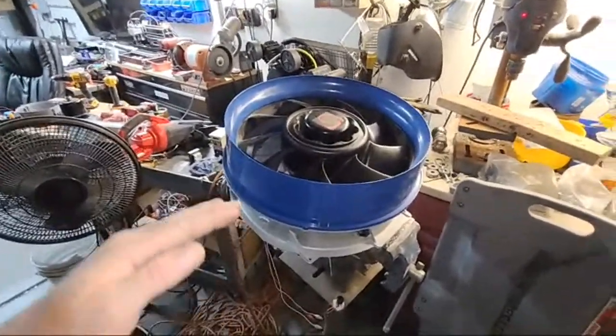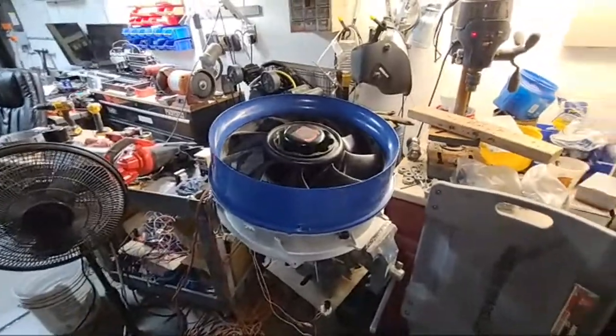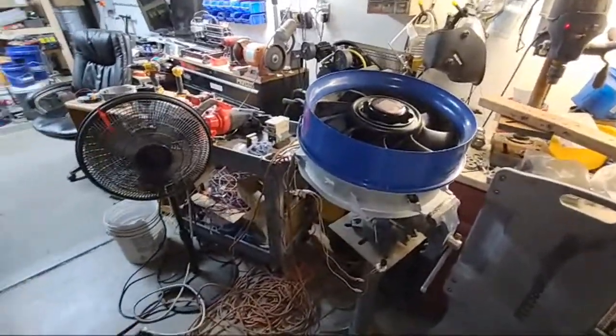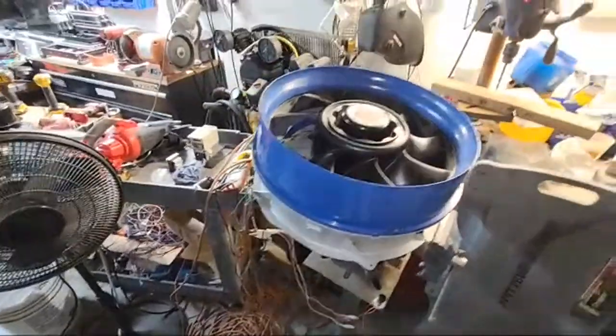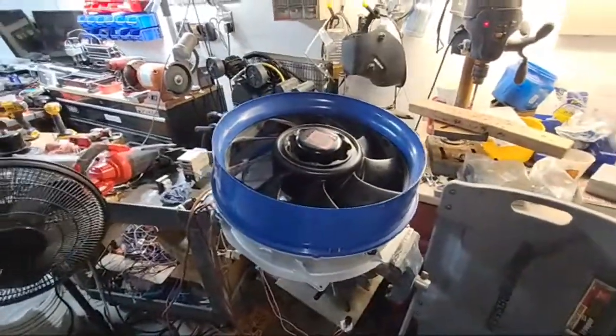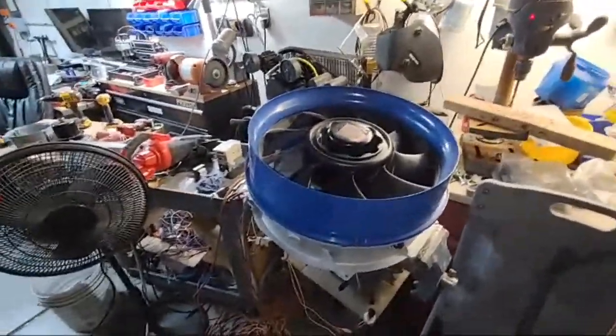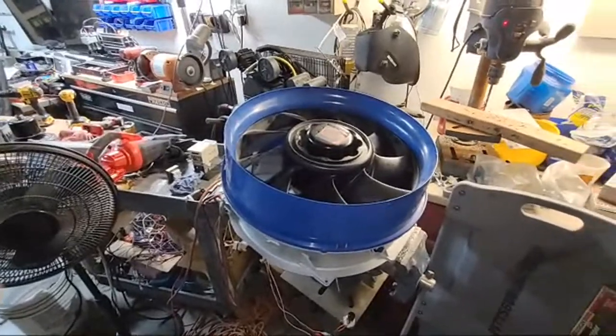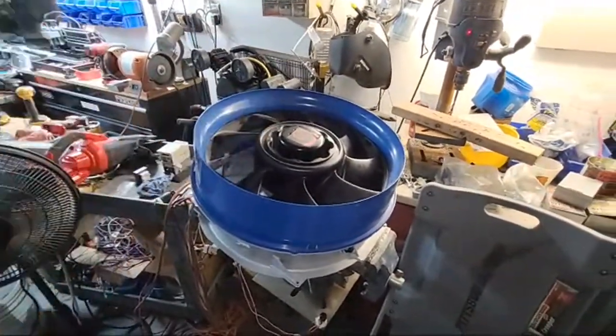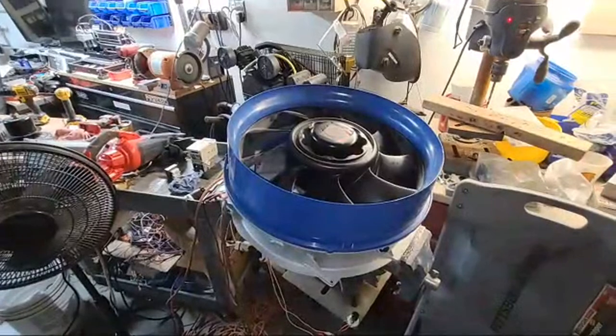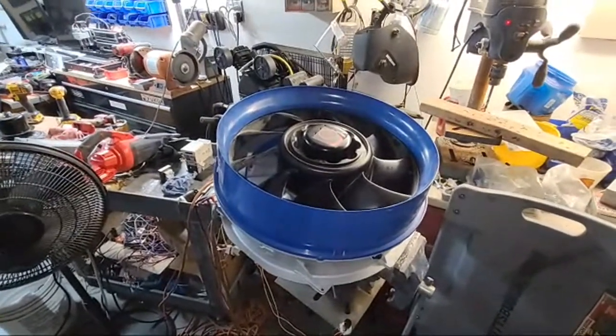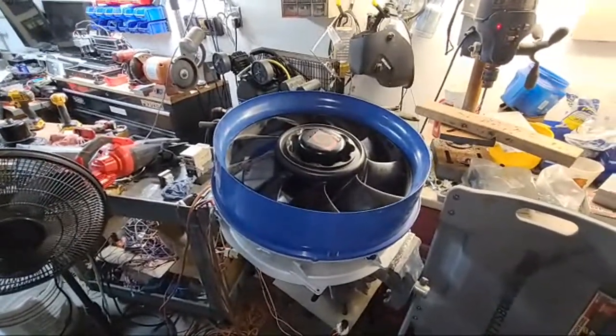that pressure will all of a sudden go up. I've caught it since we got these digital pressure gauges, Testos and Fieldpiece and stuff. Now you can sit there and record. I've caught it. It looks perfect, but then you let it run for 20, 30 minutes and all of a sudden head pressure goes up and then skyrockets to like 660 and trips. You pull out 4 ounces, 5 ounces or something like that, and then it never does it again.